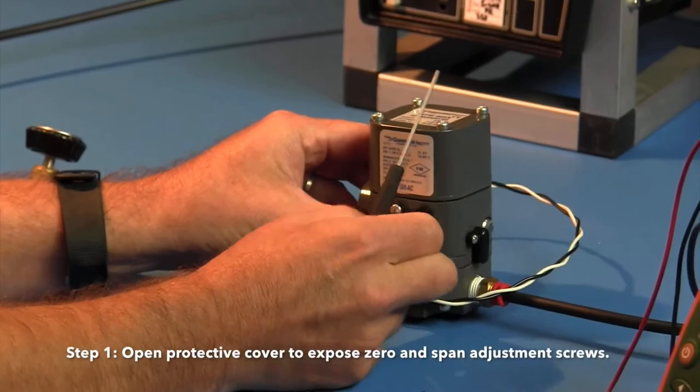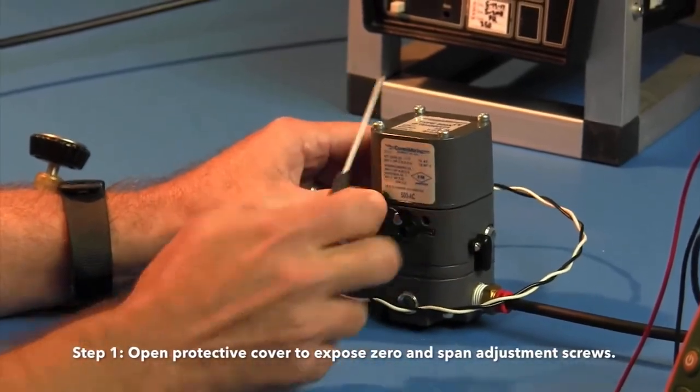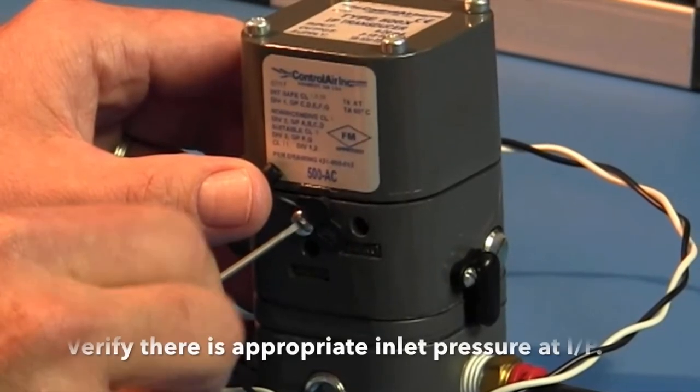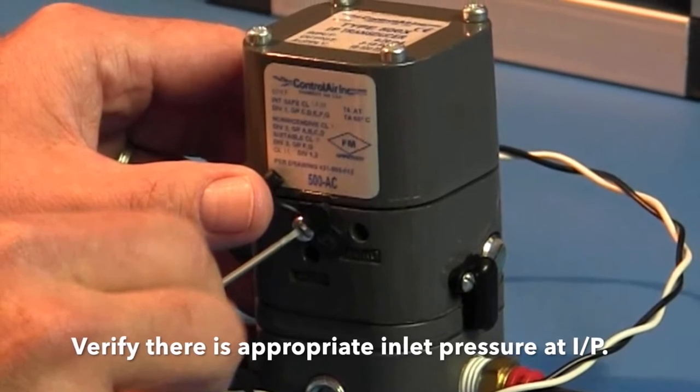Step 1. Open protective covers to expose zero and span adjustment screws. Verify there is appropriate inlet pressure at I to P.